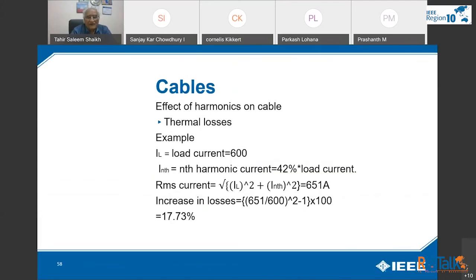Now, you can see in this example, the harmonics are increased by 42% and the losses increased to 17.73%. That's why the thermal losses increase in the cable. Sometimes the cable bursts. I have seen that, even in very big plants. So I have seen the bursting of the cables.